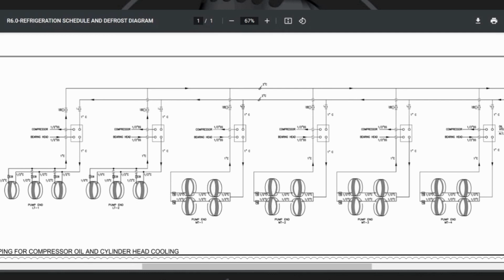By the time the water gets to the 4th head, it's 50 degrees hotter than it is when it entered the first head. Gotcha. And we didn't like that idea at all. So we paralleled these. It's okay to go through 2 heads, but not 4. So the water comes in, and we tee it off. We go into one head, out of that head into the other, and then we do the same thing on the back heads, so that all the heads are really close in temperature.